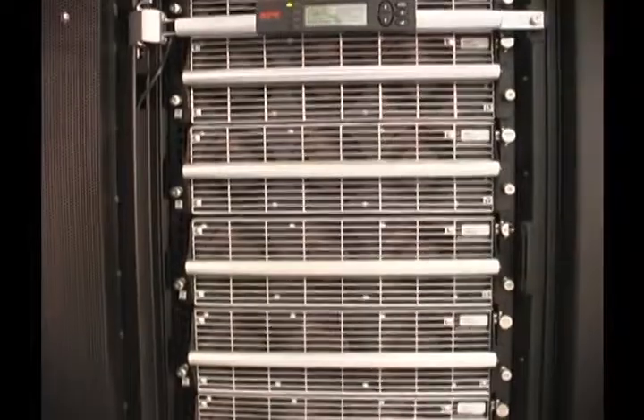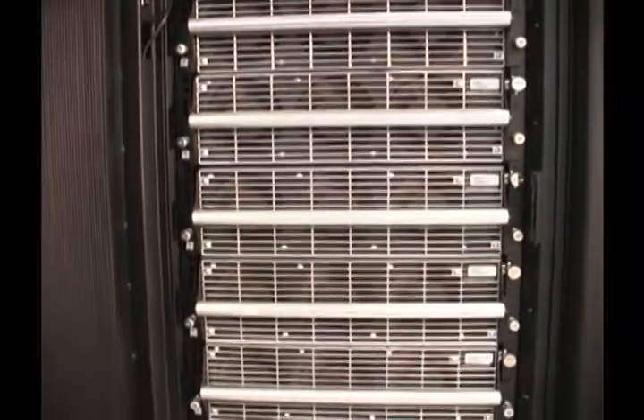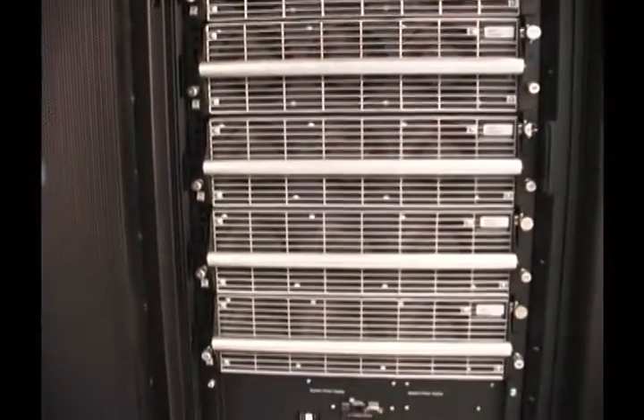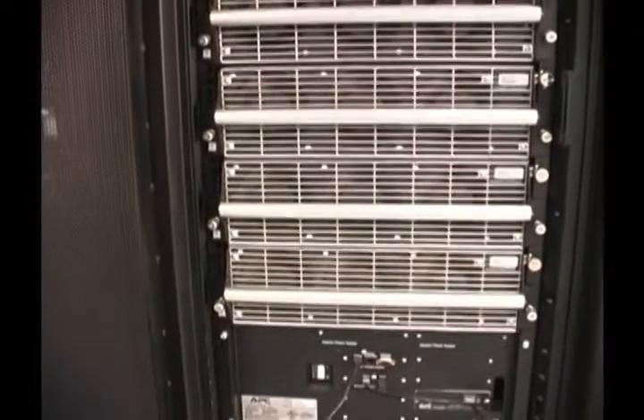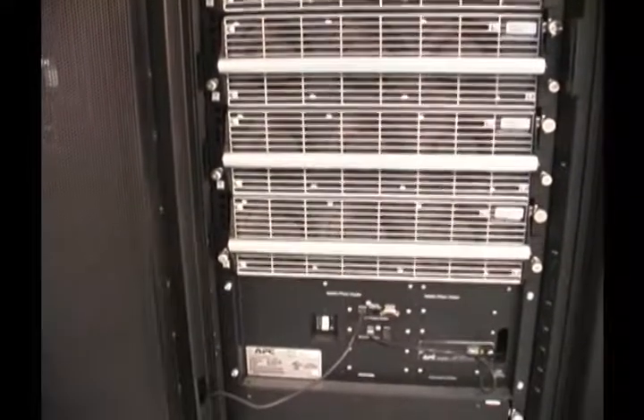Raised floors have traditionally been used in data centers for cabling management, but they reduce airflow and make it harder to maintain cooling. Utilizing best practices in data center design, the CSN data center was built without raised floors. The cabling, fiber optics, and power are all run overhead. This design allows for optimal airflow so that servers enjoy a 70-degree temperature at all times.